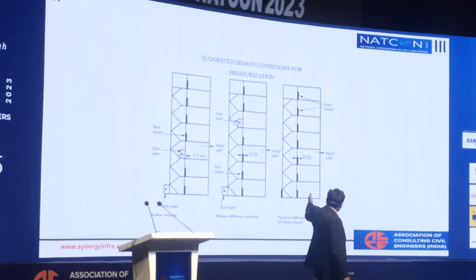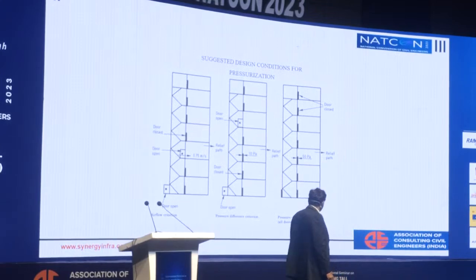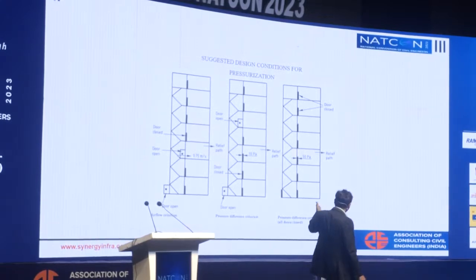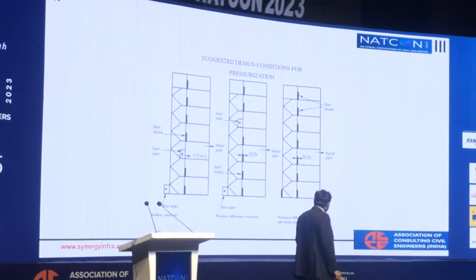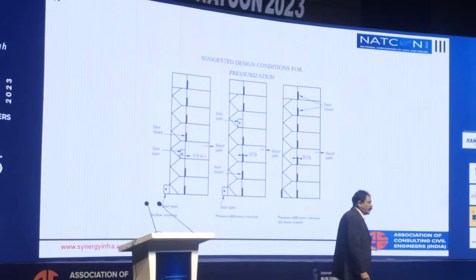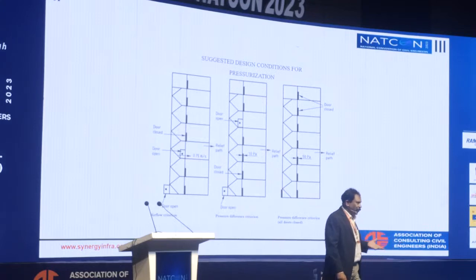So at that time, depending on the different kinds of facilities, in the last one, with doors closed, 50 pascals is to be maintained between the outside and inside of the staircase, and 10 pascals in case of 2 doors or 3 doors open. That again we need to specify. Some codes say 3 doors, some international codes say 4 doors. So we can see whatever is the best.